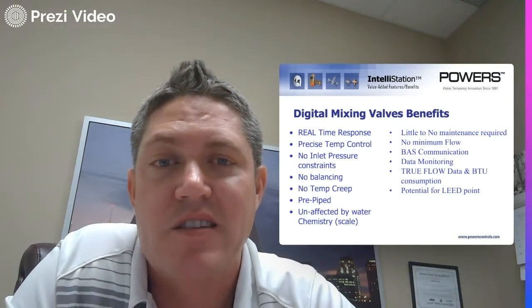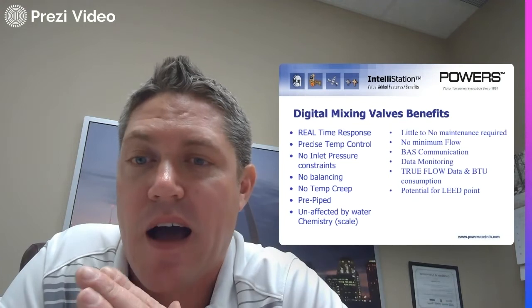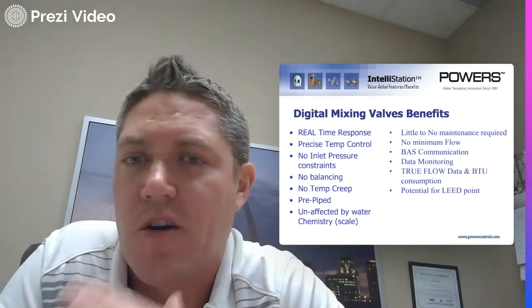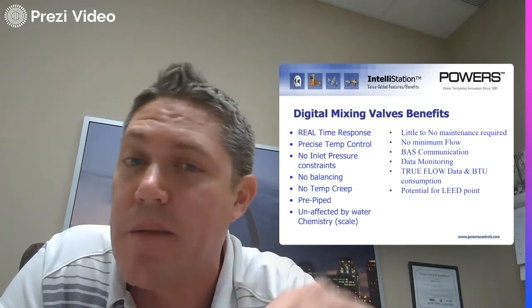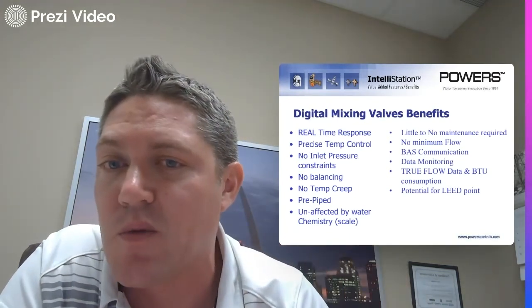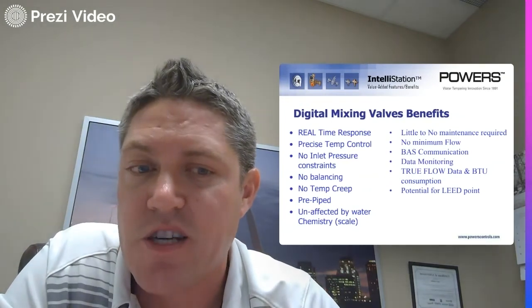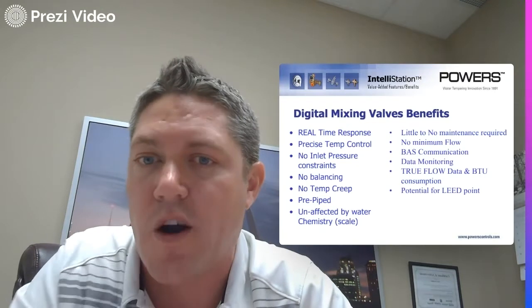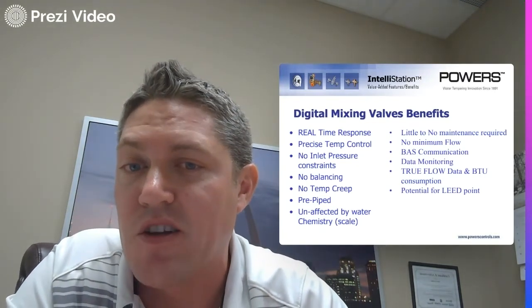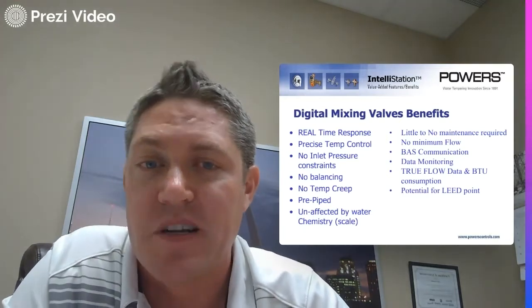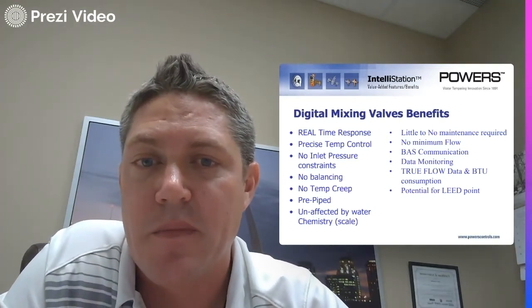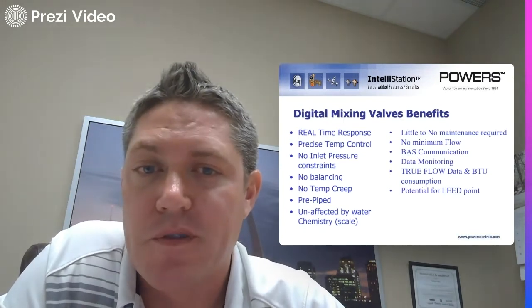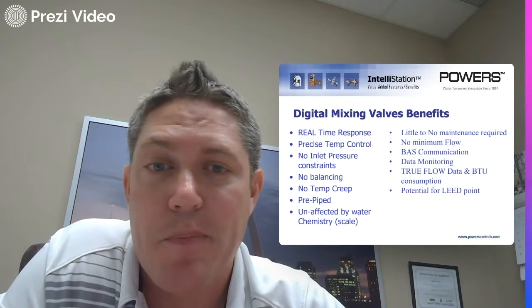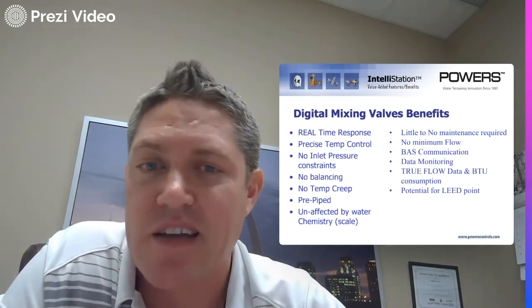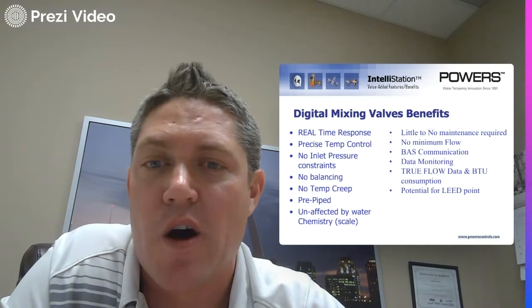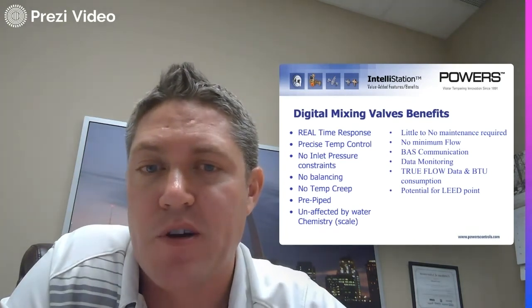It's a self-balanced system because the digital mixing valve can close off that hot inlet or that cold inlet basically 100%. And so if the temperature is creeping up overnight because too much water is going back towards the water heater in that closed loop situation, it'll just close off the hot inlet and force all the water to go back into the cold inlet on that return loop until it starts to cool, and then it'll crack back open a little bit. But it's self-balanced, no need for a balancing valve on a digital mixing system. And that in itself controls temperature creep. They're offered pre-piped, so that makes it a lot easier with the check valves and isolation valves, just basically water in, water out, and then piping up your return.